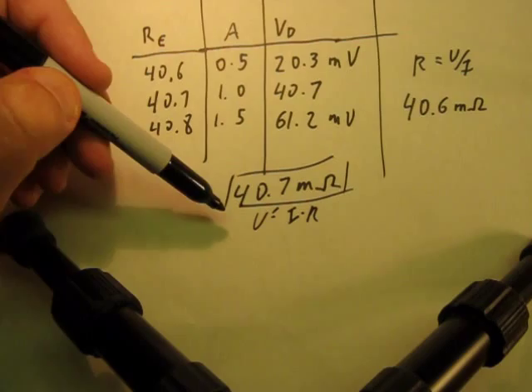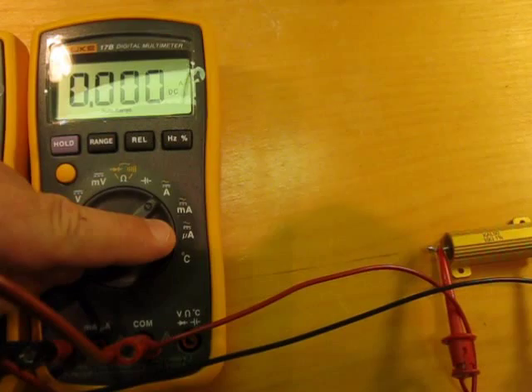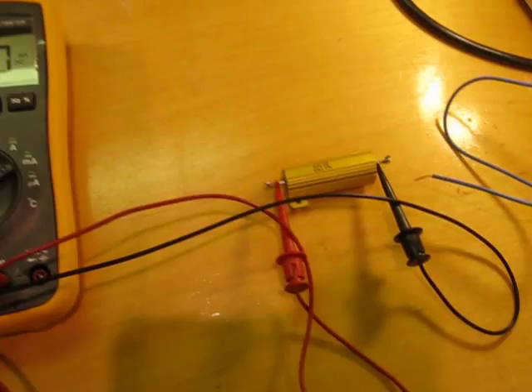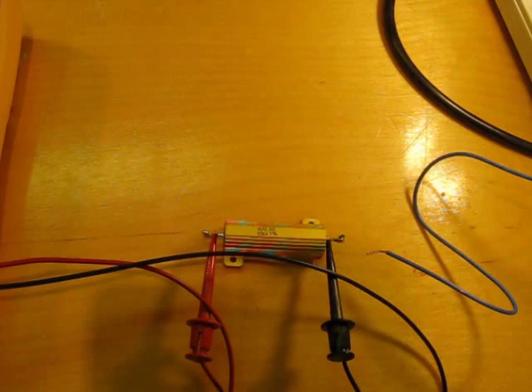So to basically round out the test, obviously you want to measure the milliamp range or the microamp range, because what's going to happen is as it switches over, it switches in a different series resistor which has an increasingly high resistance. Now the other thing you have to do, you do have to change out your resistor. I have a 10-ohm resistor here, which is really great for a 10 amp service, but as we go into the 1 amp service, you've got to pull yourself up with a higher resistance so you can create a more meaningful voltage drop.